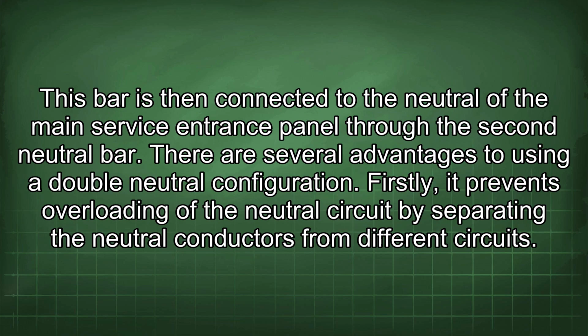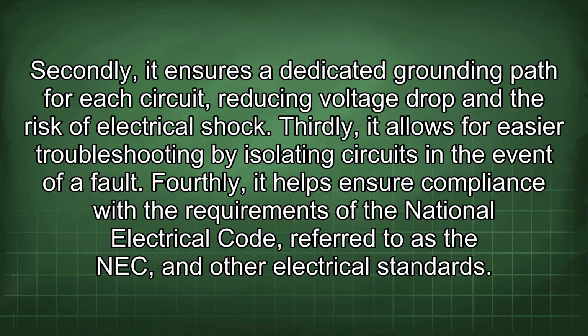There are several advantages to using a double neutral configuration. Firstly, it prevents overloading of the neutral circuit by separating the neutral conductors from different circuits. Secondly, it ensures a dedicated grounding path for each circuit, reducing voltage drop and the risk of electrical shock. Thirdly, it allows for easier troubleshooting by isolating circuits in the event of a fault.